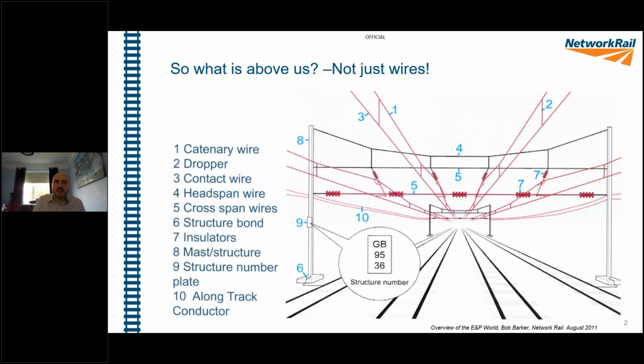And you can also see some additional along track conductors. They're marked as number 10. Now they can be different things and installed for different reasons. Some examples of that, we could have earth wires that are just used to connect all of the structures together to minimize the number of times that we need to connect to the rail. We can also have return conductors that look quite similar sometimes, but they're on smaller insulators. We also now have in the auto transformer system conductors that are along track feeders. So they are 25 kV conductors on full size insulators, and they provide part of the 25 positive, 25 negative system that we use to space our feeder stations further apart and get more capacity on the system.